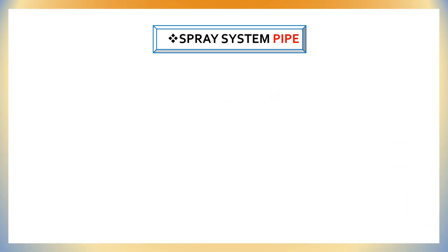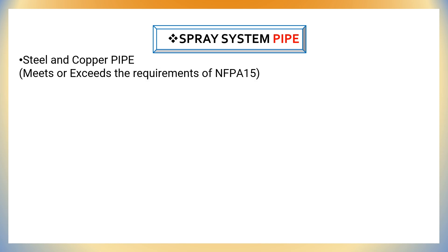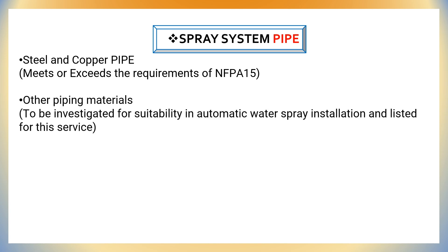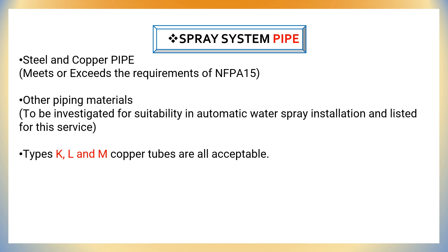The first system component is spray system piping. Steel and copper pipes can be used as per NFPA 15. Other piping materials can also be used; however, they have to be investigated for proper suitability and listed for this service. Copper tubes — which includes Type K, Type L, and Type M — are all acceptable as per NFPA 15.